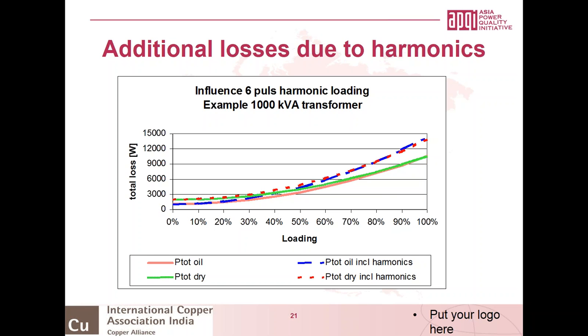you can't do it that way, because as mentioned before, the loading losses due to harmonics are not evenly distributed within a winding. So if you have a loading of 100%, you cannot say I can load it with 80% including harmonics, because the temperature at certain spots in the winding is still too high, or can be too high.